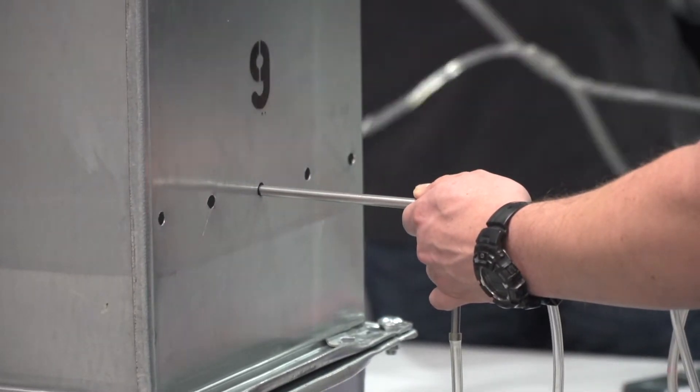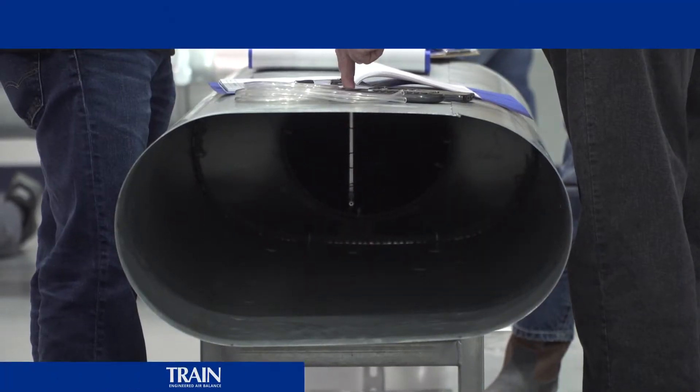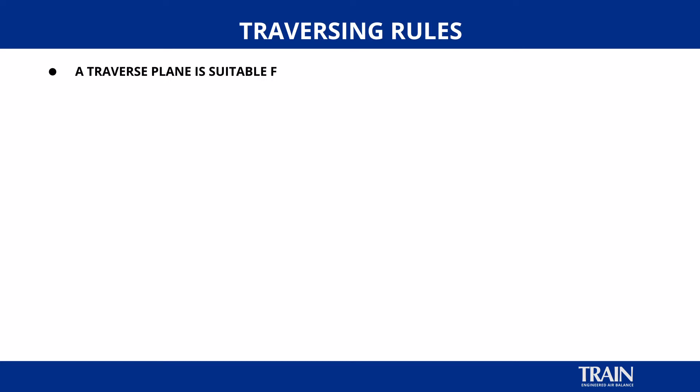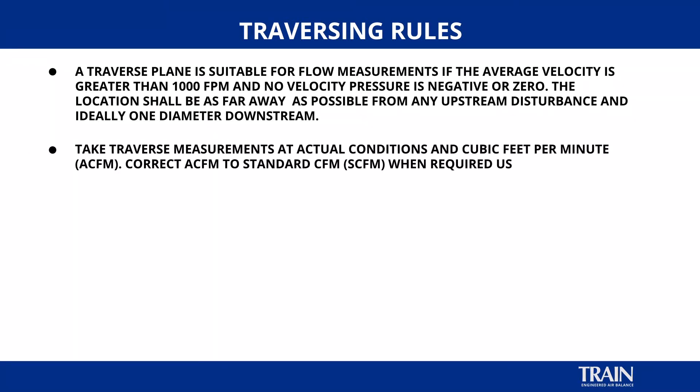There are several important rules when picking a location for conducting a traverse. In order to maintain a location that's going to contain the best chances for uniform flow, a traverse plane should be located as far away from an upstream disturbance as possible, and ideally at least one diameter downstream from a disturbance. A traverse plane is also suitable for flow measurements if the average velocity is greater than 1,000 feet per minute and no velocity pressure is negative or zero. Take traverse measurements at actual conditions in actual cubic feet per minute. If the traverse location is not at standard air conditions, a velocity correction may be required.